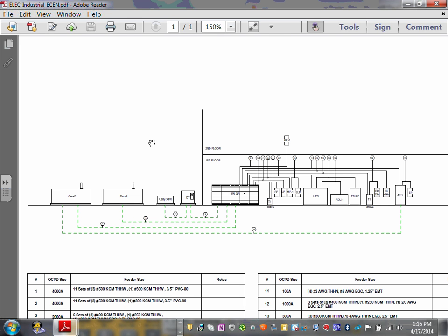When we design our risers and do our calculation, we have to make major decisions. Typically, when you walk into any building, you need a chunk of load for lights. Every single building you walk into needs some type of chunk of load for lights. If a building is big, we call this the lighting panel. Then we have another chunk of load dedicated to receptacles.